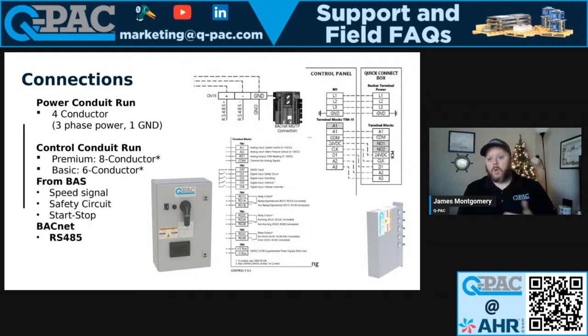Safety circuit. What do you have in this unit that's designed as a safety circuit? This could be high pressure, low pressure cutouts. This could be freezestats. This could be damper position switches, end switches, you name it. There's a whole lot of things. Door switches, safety cutouts, fire, smoke dampers, a lot of things like that. So that safety circuit, we'll talk about further, is needed for minimum operation in hand mode, and then obviously it'll be needed for further operation.